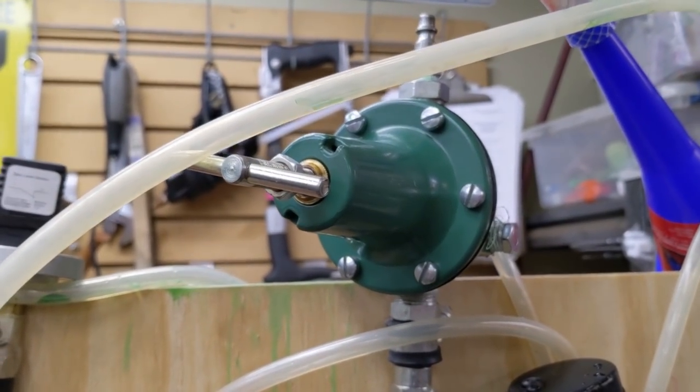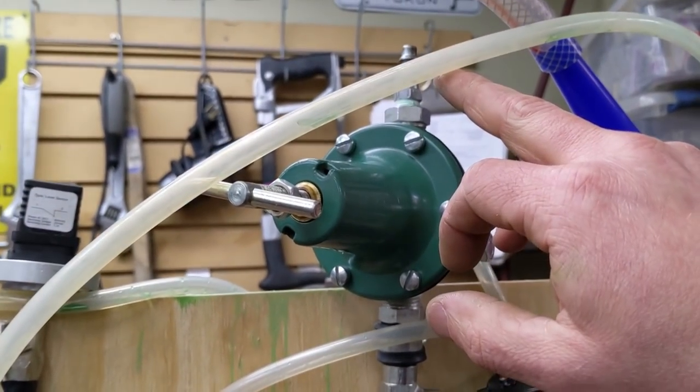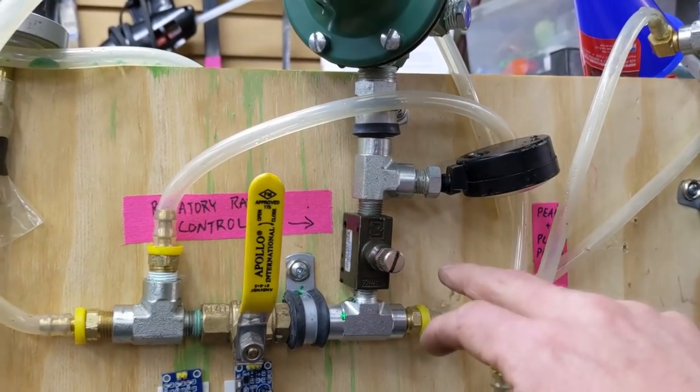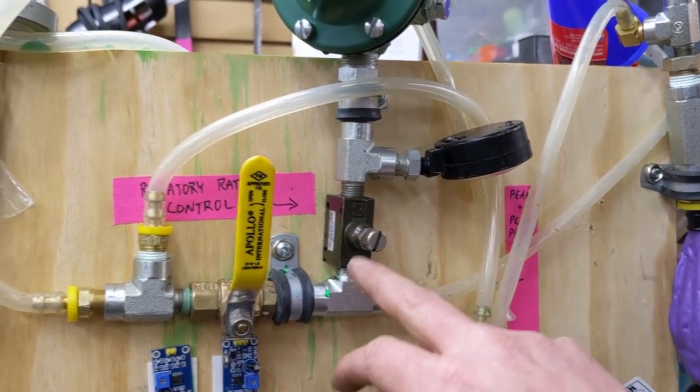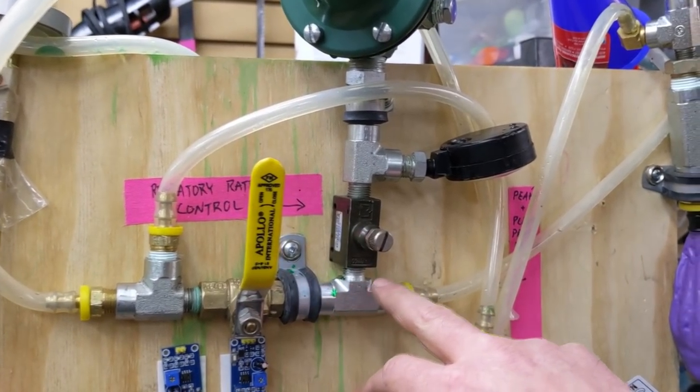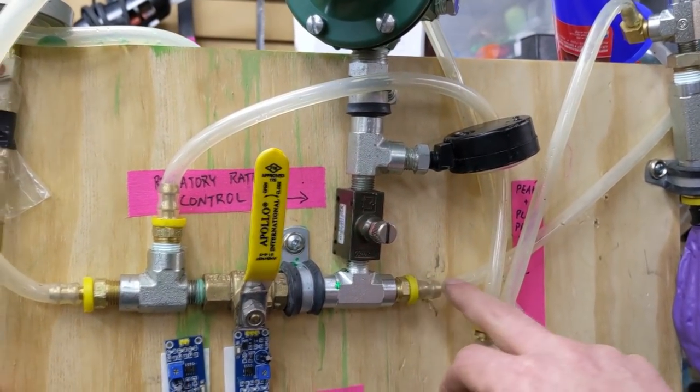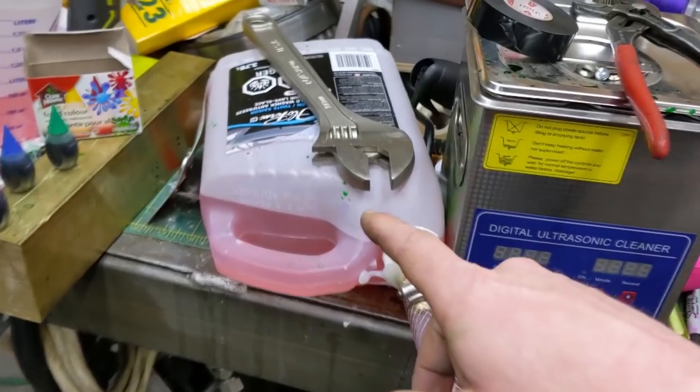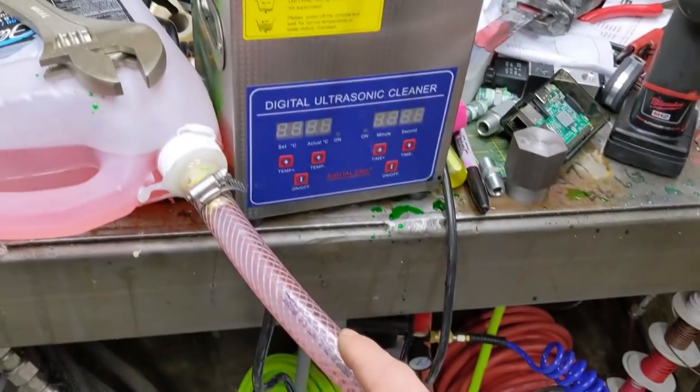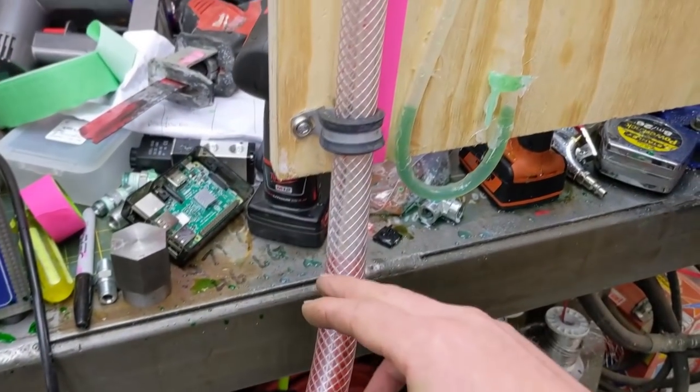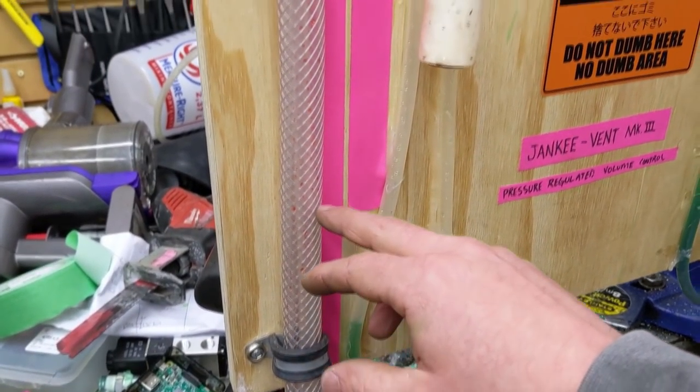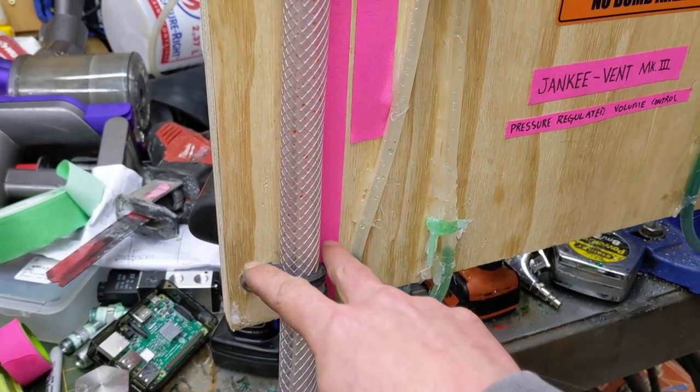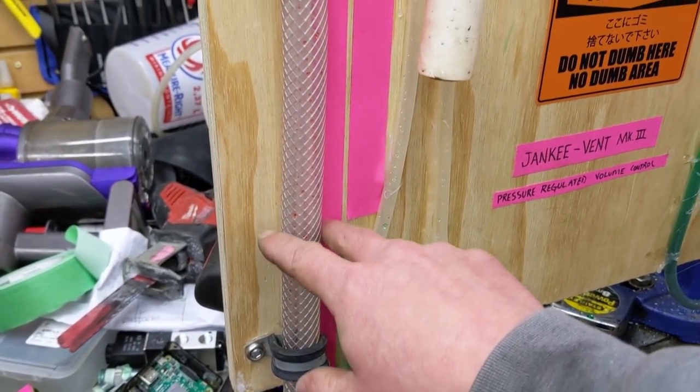Oh here's the typical embodiment. We have a pressure reducing valve, air in, pressure reducing valve, a needle valve. You just have a gauge here just for close proximity to see what's going on. And what we do is we set this so that it fills a bladder over here. And this is closed loop here, because as the bladder expands, we come over here to a manometer. So we can set the amount of tidal volume by monitoring how high the manometer rises.